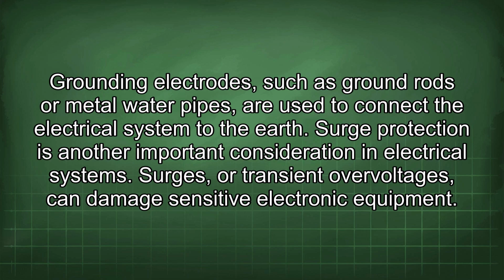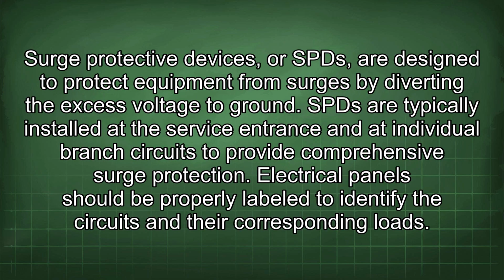Surge protection is another important consideration in electrical systems. Surges, or transient overvoltages, can damage sensitive electronic equipment. Surge protective devices, or SPDs, are designed to protect equipment from surges by diverting the excess voltage to ground. SPDs are typically installed at the service entrance and at individual branch circuits to provide comprehensive surge protection.